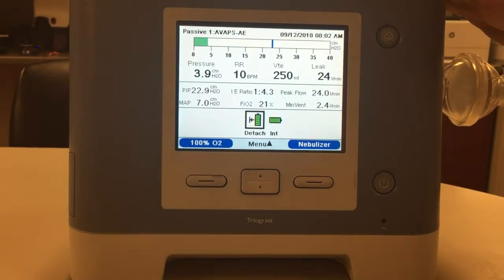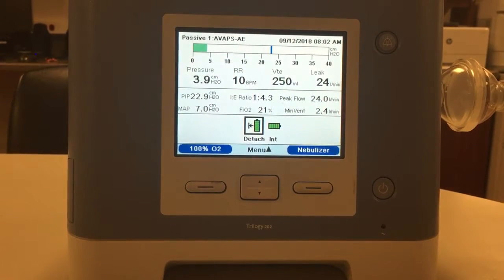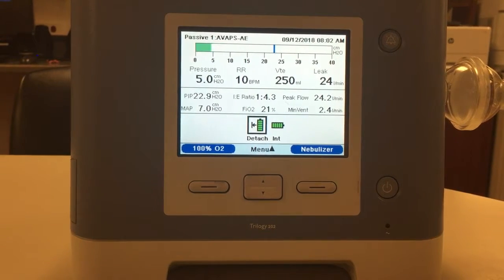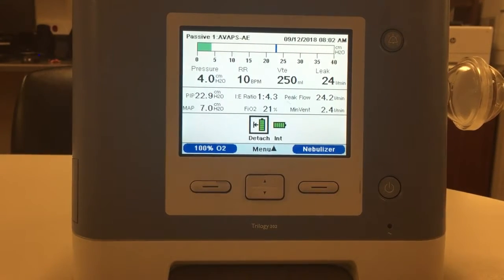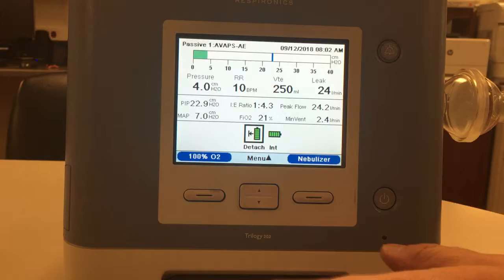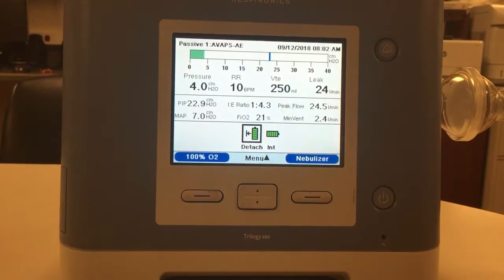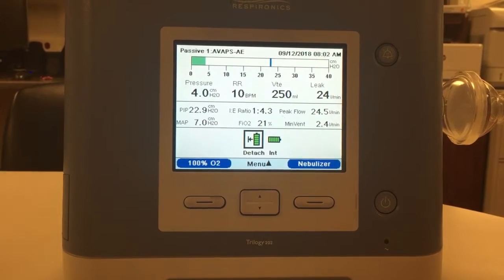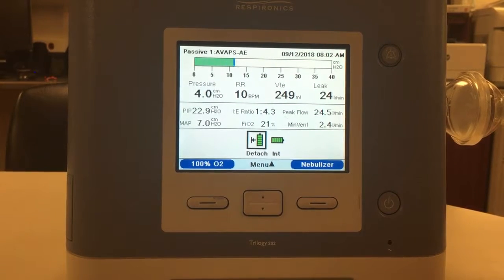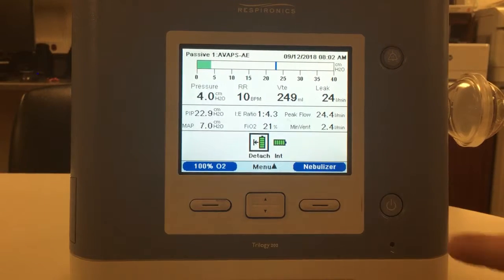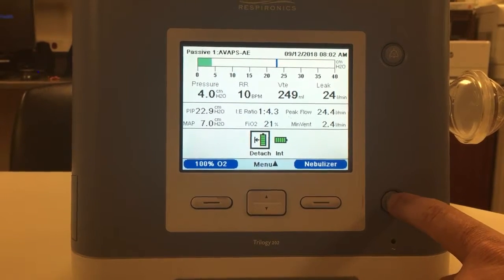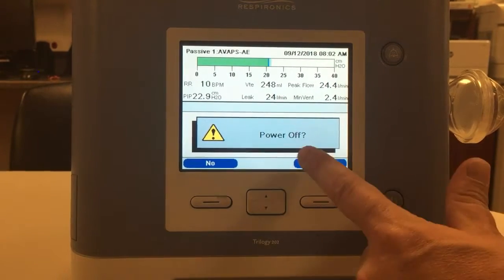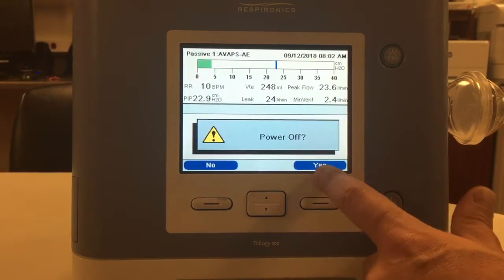So there is a secret handshake, as home equipment typically does have, to get into a clinical or provider menu. Now, this can be done with the ventilator running, and typically to change other or all the parameters, the ventilator should be off prior to, which I will turn off now. As you can see, it's prompting me to power off, and I want to make sure that yes, you do want to turn off the ventilator.